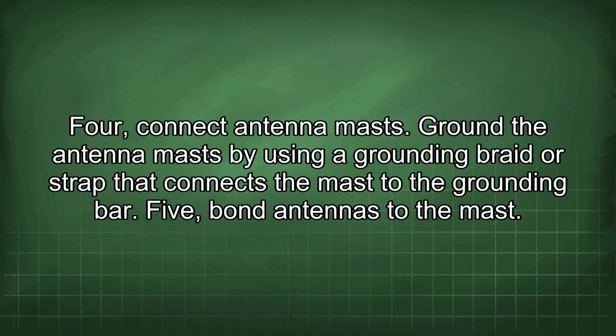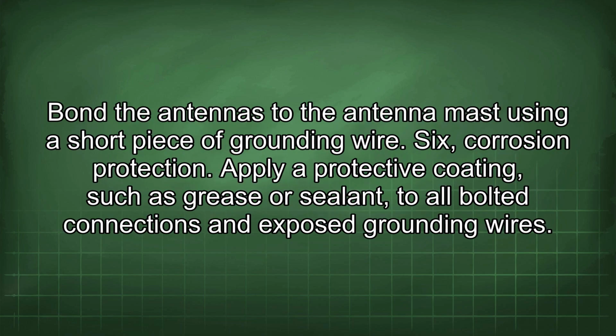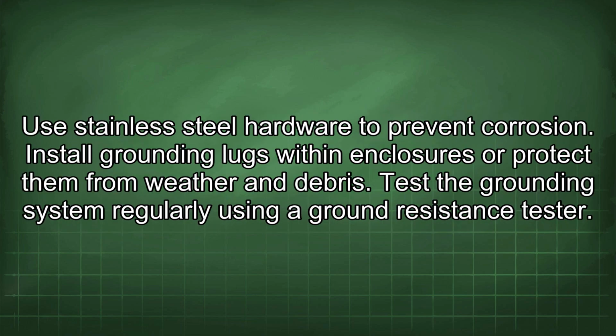4. Connect antenna masts. Ground the antenna mast by using a grounding braid or strap that connects the mast to the grounding bar. 5. Bond antennas to the mast. Bond the antennas to the antenna mast using a short piece of grounding wire. 6. Corrosion protection. Apply a protective coating, such as grease or sealant, to all bolted connections and exposed grounding wires. Use stainless steel hardware to prevent corrosion. Install grounding lugs within enclosures or protect them from weather and debris.